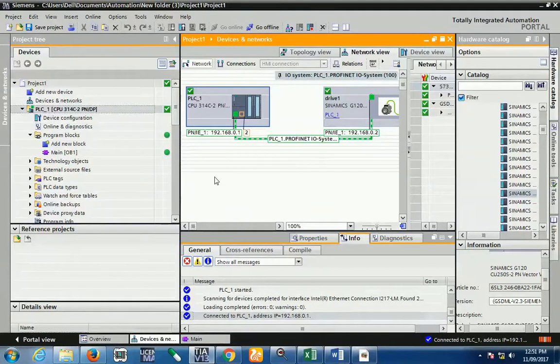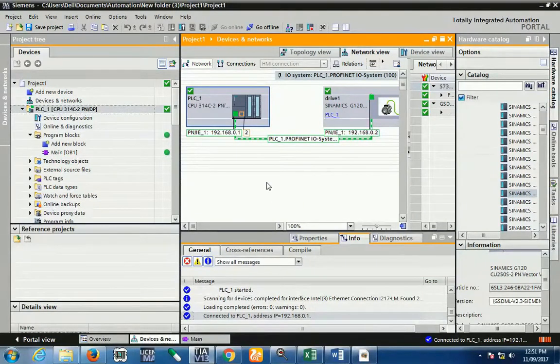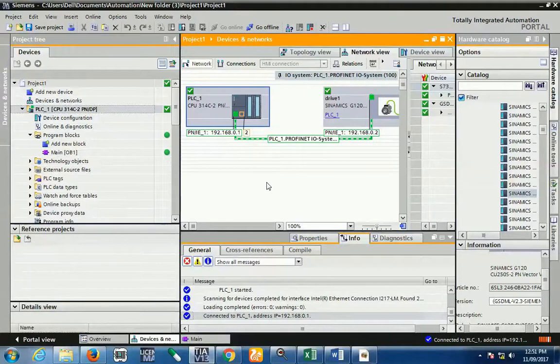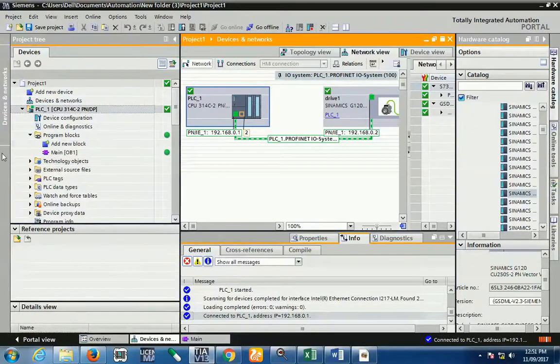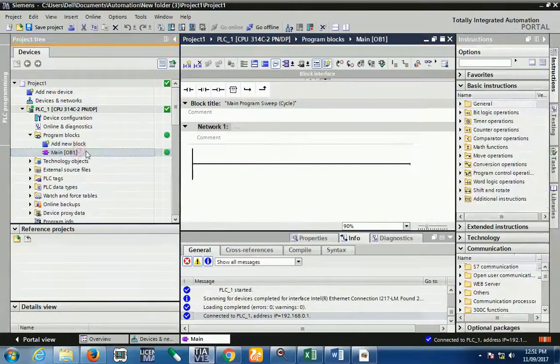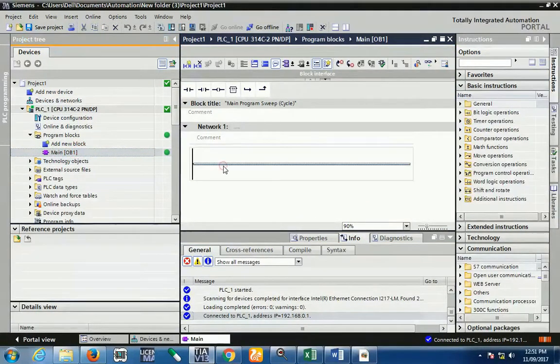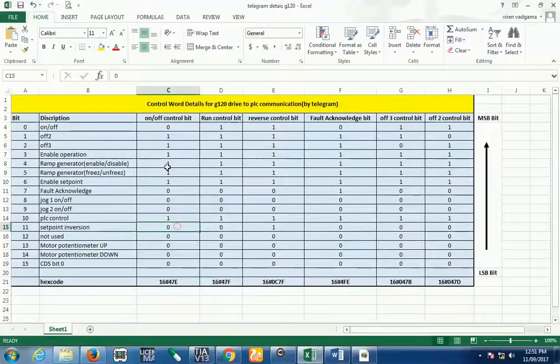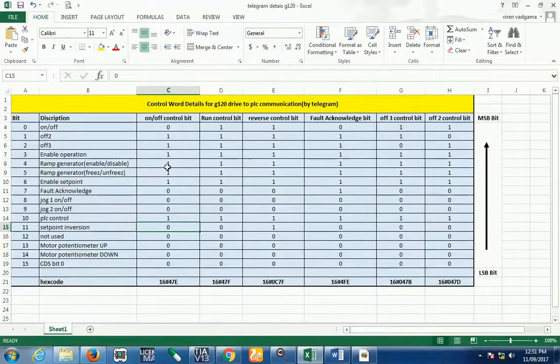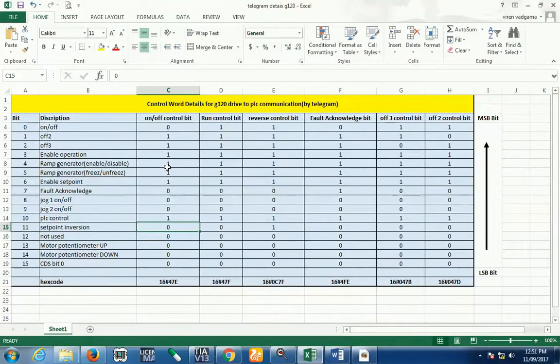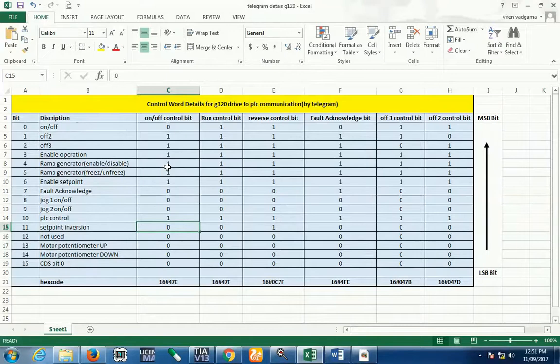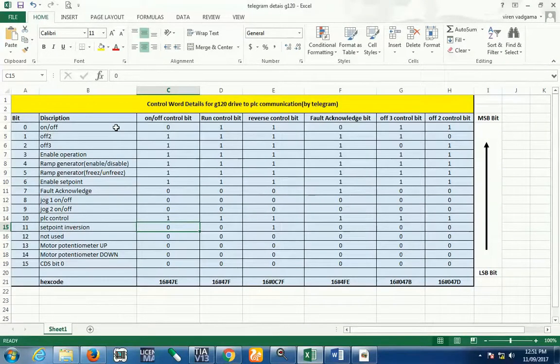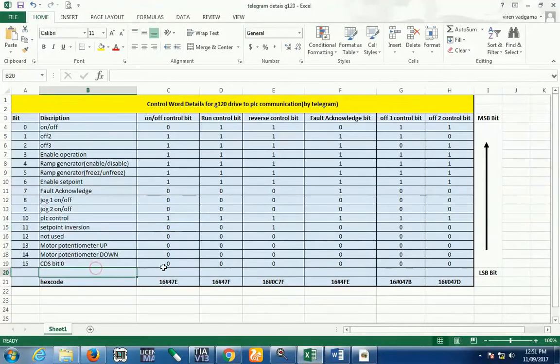Now right now your communication process is done. So here now we will configure the control and the reference data in main block. So how to configure? There is all I already told you. Your first word is the control word and the second one is the reference word. So in the reference word, we have sent the directly data reference. The first word is the control word. So in the one control word, there is 16 bit. So this is the configuration of the bit. First command is the on off control. Second is the run control. And if you change the direction, means once we have just transferred this code, it is a reverse control bit. So this is the condition of all the bits for on off control bit.